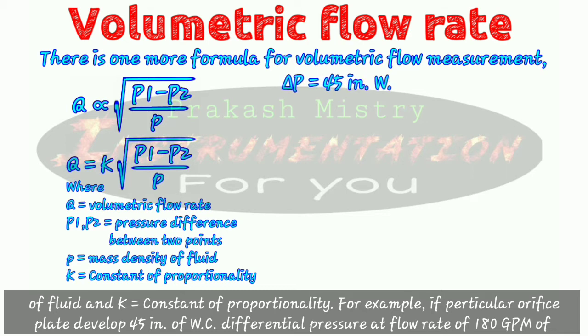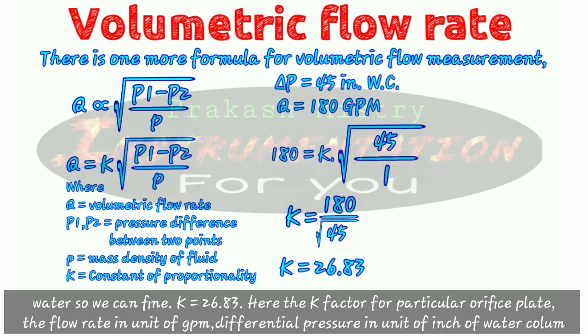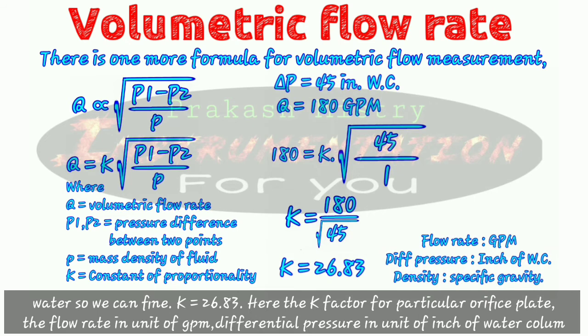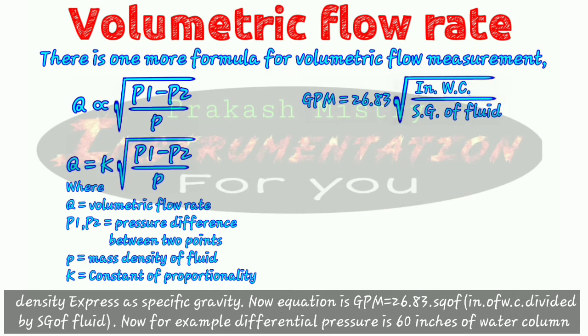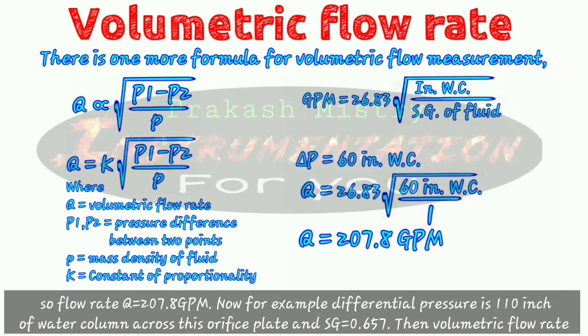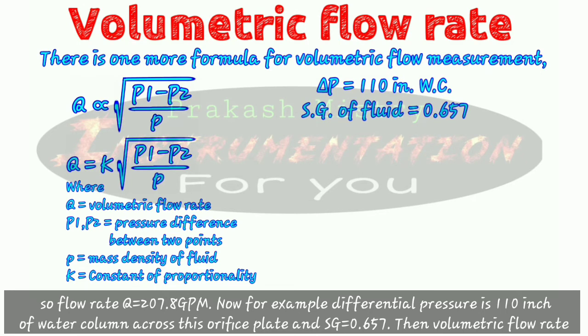For example, if a particular orifice plate develops 45 inches of water column differential pressure at a flow rate of 180 gallons per minute of water, we can find K equals 26.83. The K factor for this orifice plate has flow rate in gallons per minute and differential pressure in inches of water column, with density expressed as specific gravity. So the equation becomes: GPM equals 26.83 times the square root of (inches of water column divided by specific gravity). For example, if differential pressure is 60 inches of water column, the volumetric flow rate is 207.8 gallons per minute. If the differential pressure is 110 inches of water column and specific gravity is 0.657, then Q equals 347 gallons per minute.